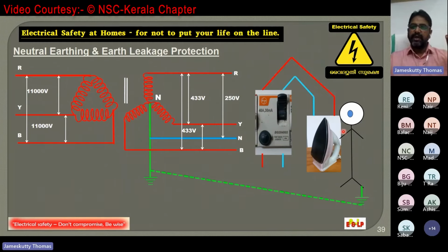See here, actually, this person can withstand only up to 30 milliampere current, because in a human body, the heart is the most sensitive part. We will study it later. So here we should get the protection for 30 milliampere, or I can say this RCCB is rated for 30 milliampere. When there is a difference of 30 milliampere current between this phase and neutral, the RCCB will trip and the person will be safe.